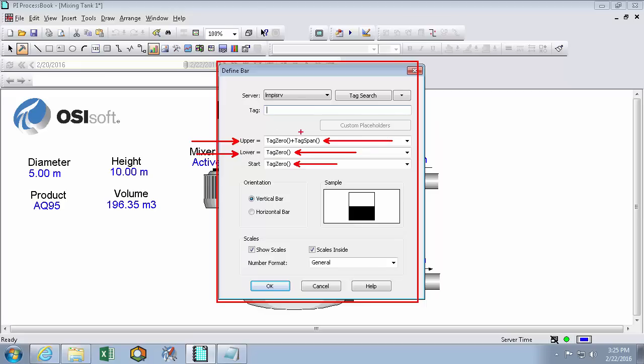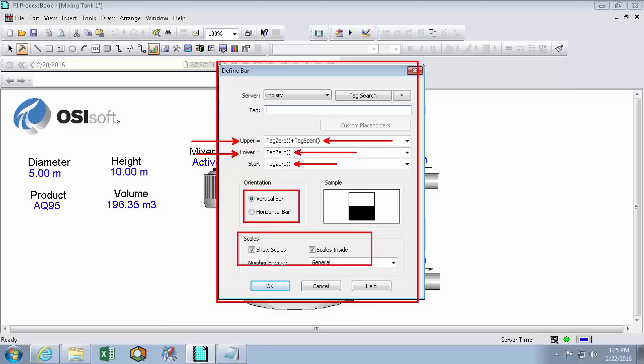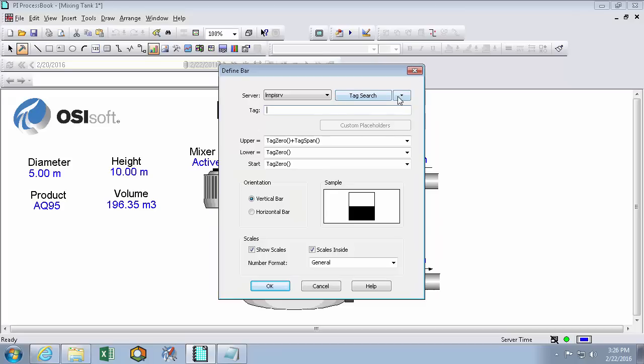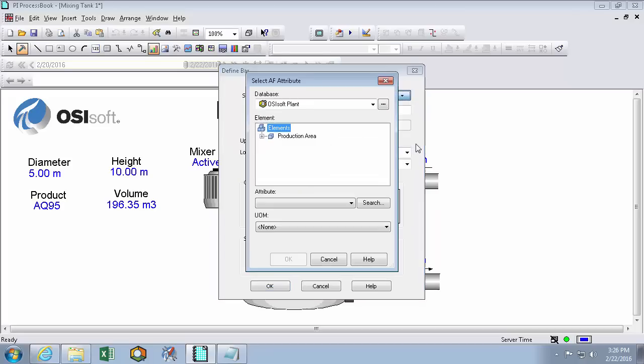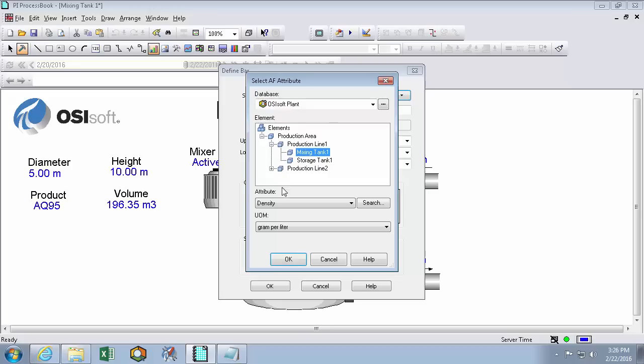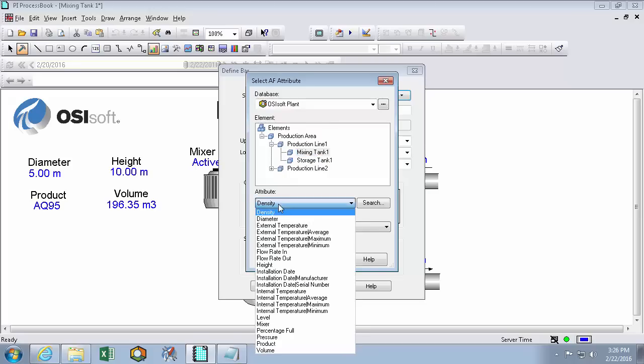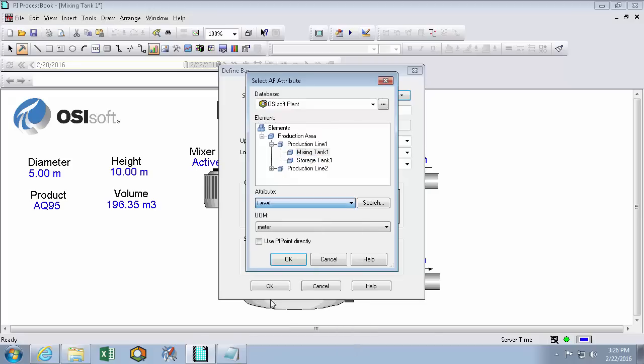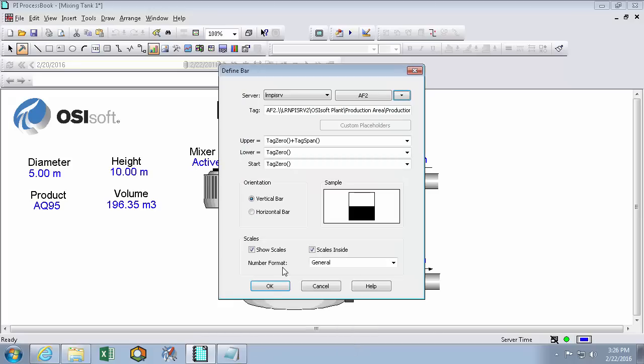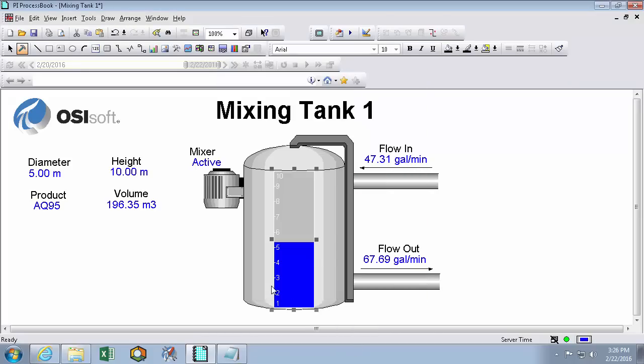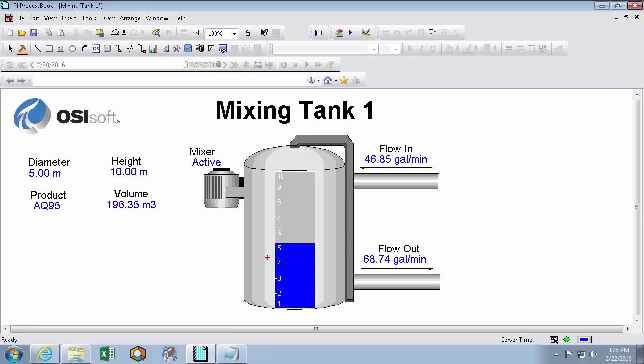So this current configuration is the start of the bar graph is going to be at the expected zero of the PI point, and the expected upper value of the bar graph is going to be the zero of the PI point plus the range or the span of the PI point. And the default orientation is set to vertical rather than horizontal. And we're going to see the scales inside. So let's define our data source as again from the AF tree. We'll use mixing tank 1's level attribute. And now we see a level bar that kind of looks like we might have a level of fluid in this tank.